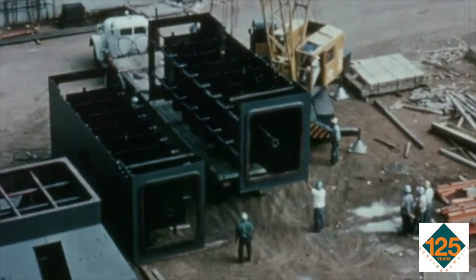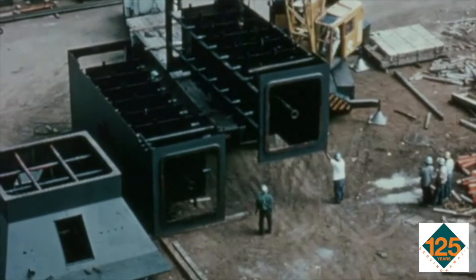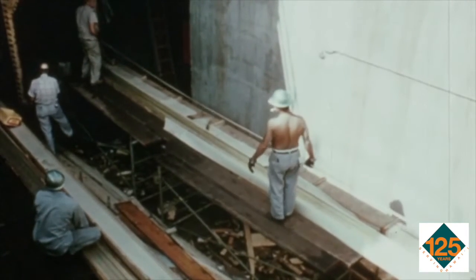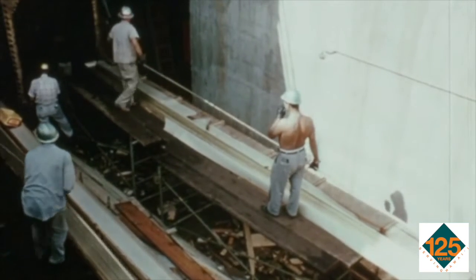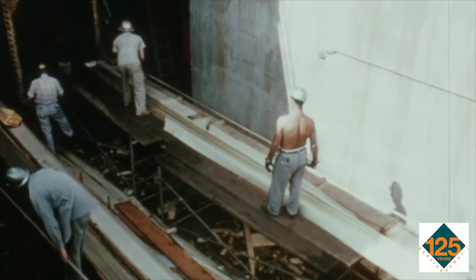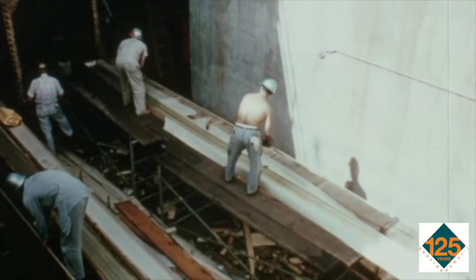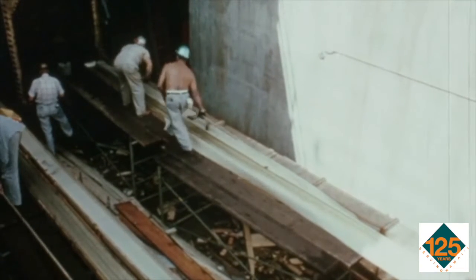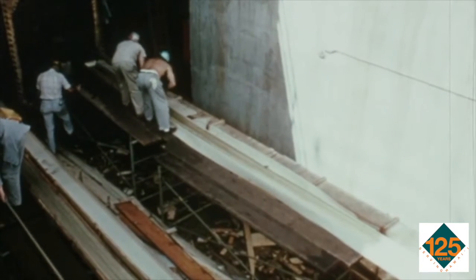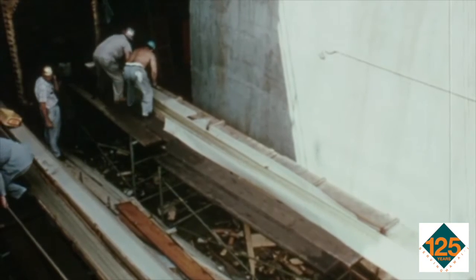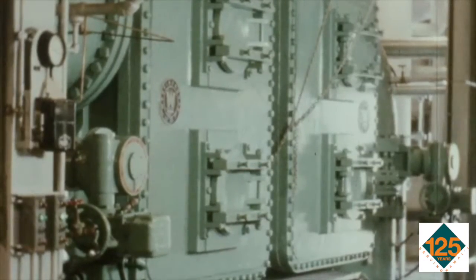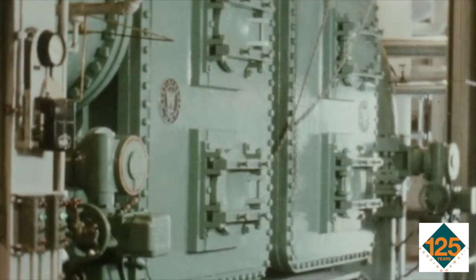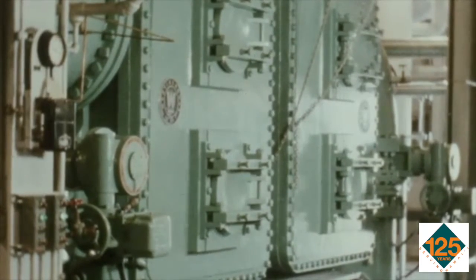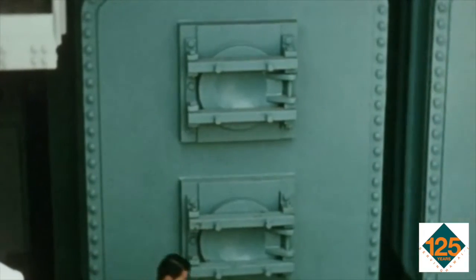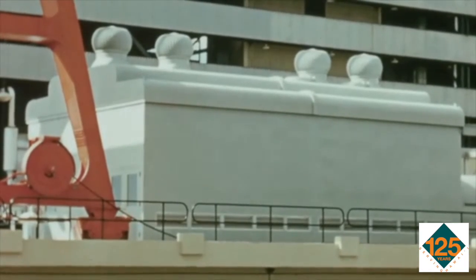After the steam has passed through the turbine, it is converted back into water in a large condenser. This condenser is installed under the low-pressure turbine and is fitted with 33 miles of aluminum brass alloy tubing. These tubes carry the salt water, which cools and condenses the steam passing over the outside of the tubes. When completed, the turbine generator is enclosed in a weatherproof house.